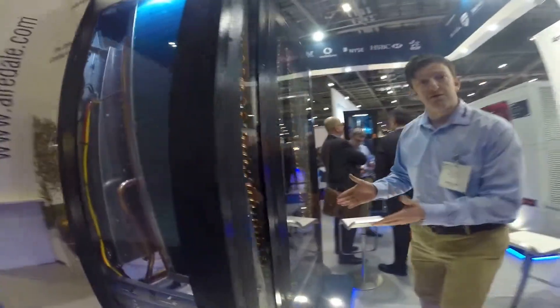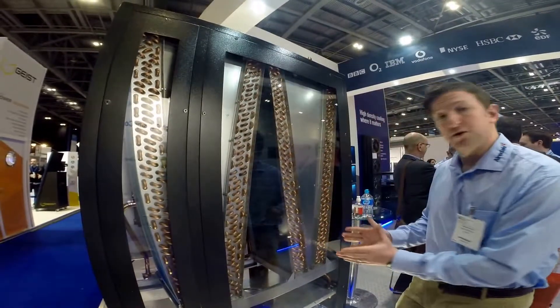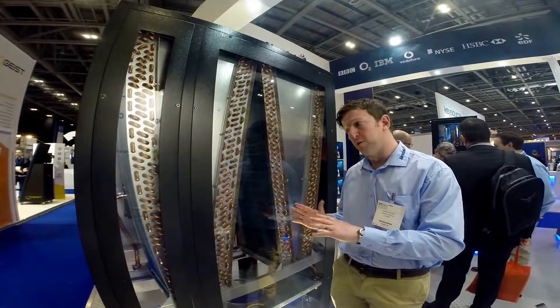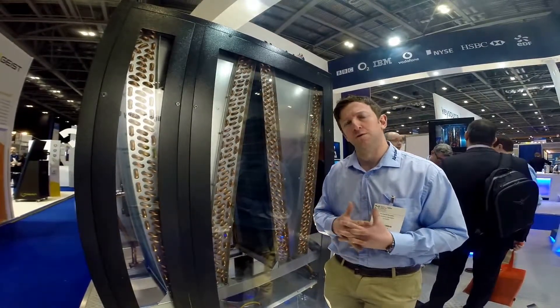If we just go around the back of the unit, you can get a better idea of the coil configuration I'm talking about. This unit will cool up to about 90 kilowatts in the range with this coil configuration. It will then go above that to about 233 kilowatts. The coil configuration will change from the V-block to a slab coil, taking you to about 233 kilowatts.